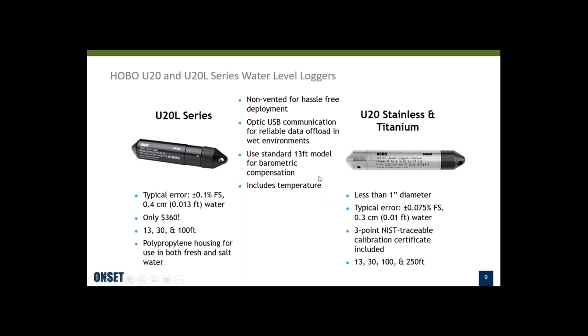We recommend using the 13-foot model of either series for doing barometric compensation. These loggers also record temperature. The U20L series typically has accuracy around 0.1% of full scale. They start at $360 US dollars with three different ranges, and the polypropylene housing is suitable for fresh or salt water. The metal housing U20 series loggers have a smaller diameter — less than an inch — slightly better accuracy, include a three-point NIST traceable calibration certificate, and have four different ranges including a deeper range for higher pressure situations.